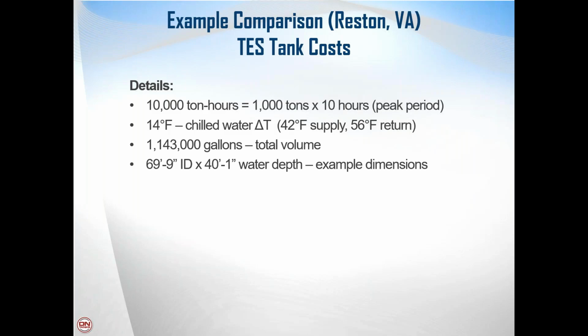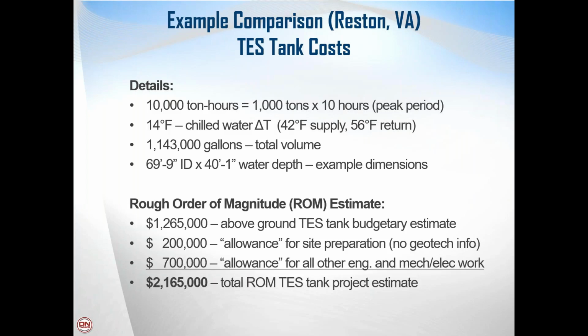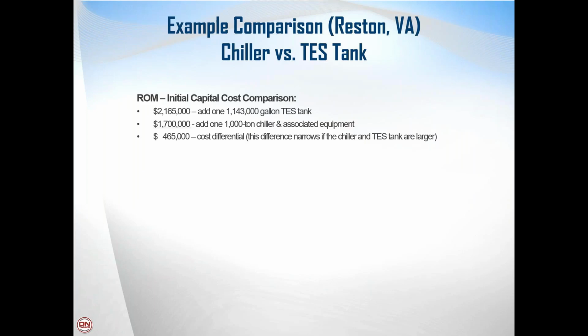But we can build that tank in any custom circular size that would fit on that campus. But a rough order of magnitude of cost for that system is about $2.1 million for that tank. That includes the thermal energy storage tank at $1.265 million, an allowance for the site work to prep the site for the tank, an allowance for all the other work outside of the tank, the piping interconnections that are required, the instrumentation and controls, and the engineering of the work outside of the tank. So that's how we come up with the $2.165 million.